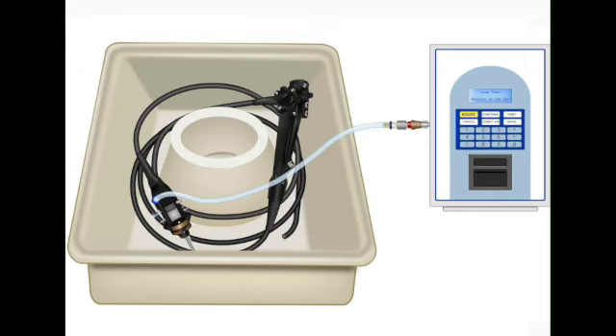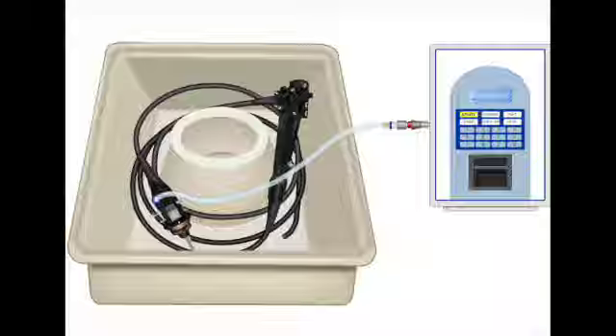Wow. Okay. So outcome number one, under that constant pressure, you see the bending section, that flexible tip, start to inflate. It distends like a little balloon. And that's good. It's the better bad news. It means the inner channels are probably still sealed, but the outer sheath has a hole. In that case, you can submerge the scope, clean it carefully, and then send it for repair. Following the IFUs, of course. Of course, the IFUs, the manufacturer's instructions for use, they are the gospel. You never, ever deviate. Okay, so that's the better bad news. What's the really bad news?